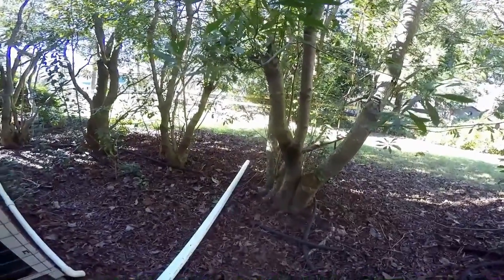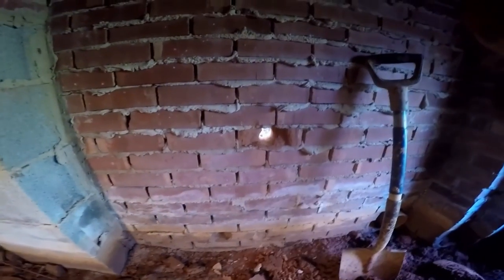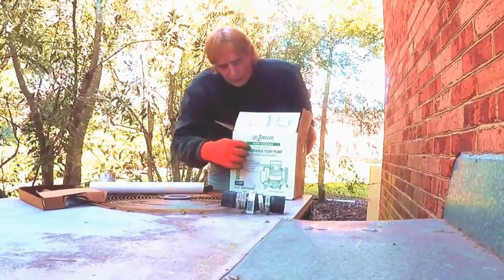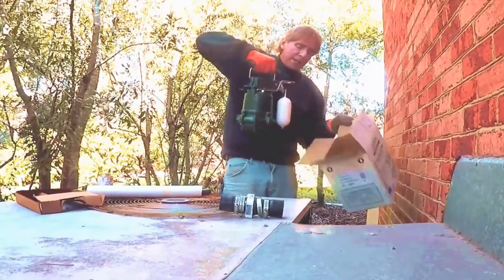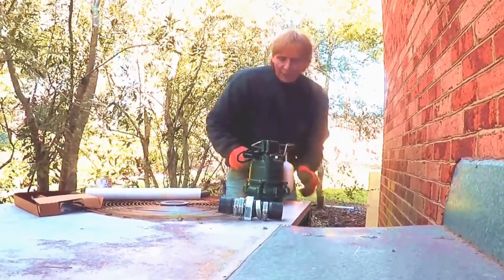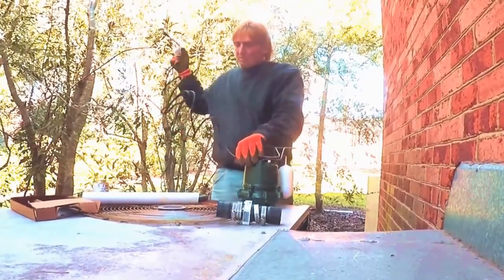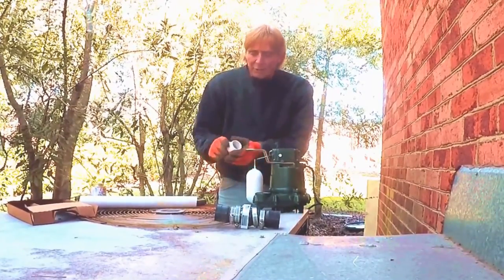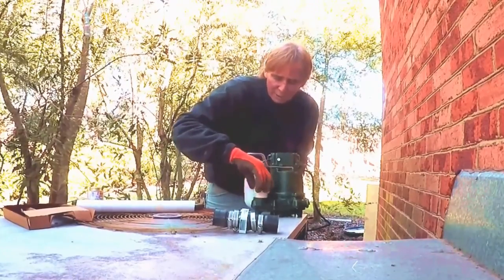Here's our sump hole for the pit - you can see we got it down there pretty good. Here's where we cored the foundation and that's the discharge. We're almost done. The next thing we're going to do is set up our Zoeller M53, called the Mighty Mate - one third of a horsepower, very powerful pump, cast iron body, very heavy actually for its size. First thing we're going to do is put a threaded male inch and a half adapter right into the discharge of the pump and screw that in hand tight.